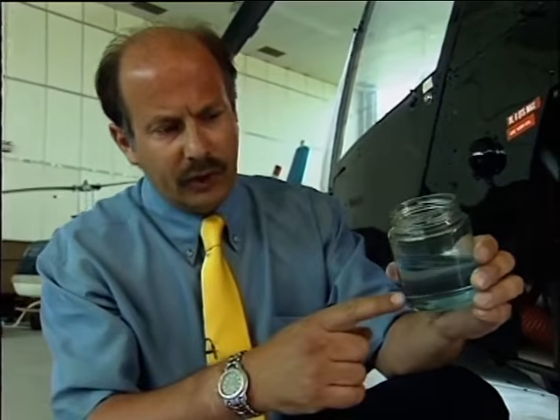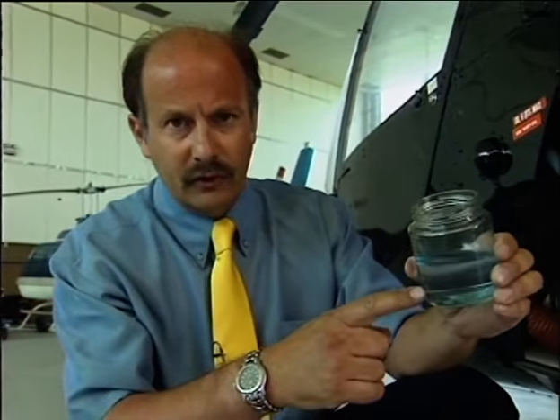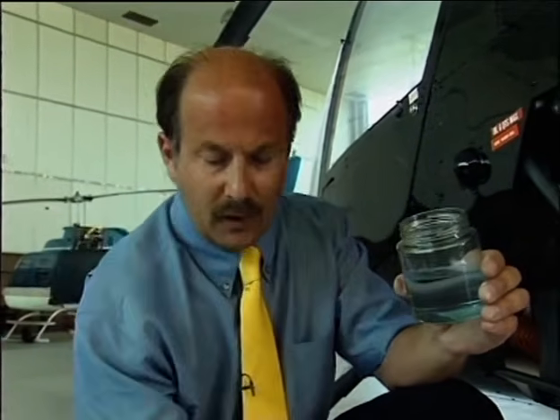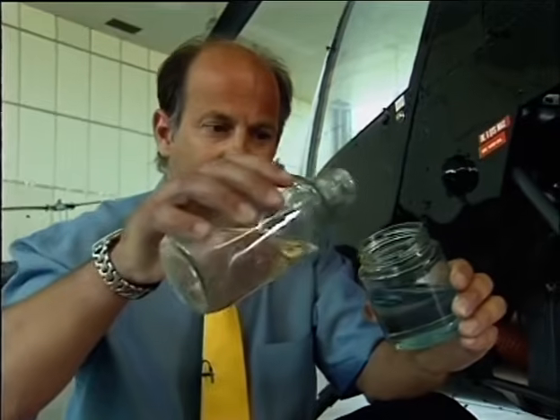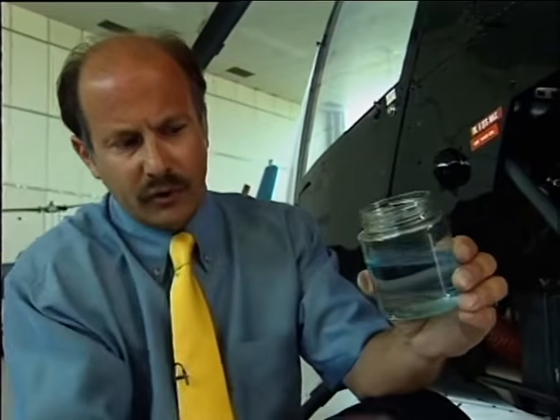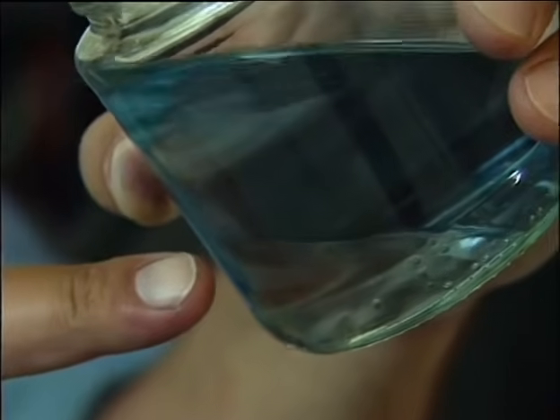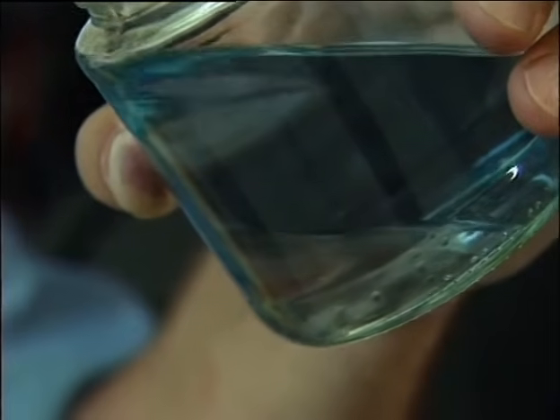So here we have an example of uncontaminated fuel. What you're looking for in contamination are small particles suspended within the fuel, and water. If I add some water to the fuel sample, you can see water, being heavier than fuel, will be at the bottom of the container. That concludes the sampling checks.